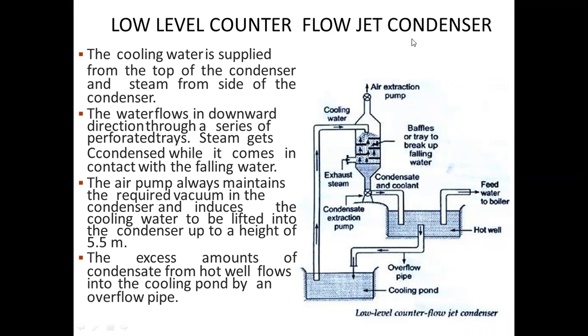Now the low level counter flow jet condenser. You can see this is a low level counter flow jet condenser. In this case, cooling water enters from the top side and exhaust steam enters from the bottom side. There are a few baffle plates so that the steam cannot go directly outside. When it comes in contact with the water, it releases its heat and air is removed with the help of an air extraction pump, and the condensate collected at the bottom can be removed with the help of a condensate extraction pump, right? The cooling water is supplied from the top of the condenser and steam from the side of the condenser. As already mentioned, the water flows in a downward direction through a series of perforated trays.